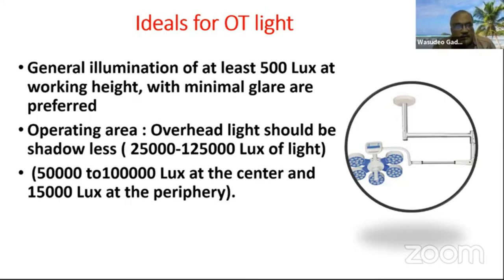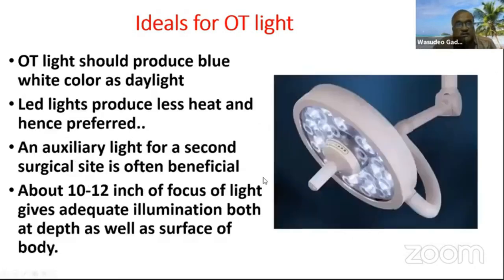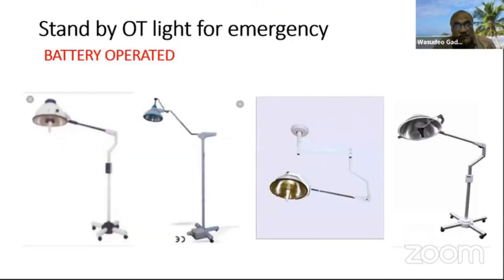The pendant system or breeder is ideal. The OT light should provide general illumination of at least 500 lux at working height with minimal glare. The operating area overhead light should be shadowless. OT lights should produce blue-white color like daylight. LED lights produce less heat. An auxiliary light for a second surgical site is often beneficial, and about 10 to 12 inches of focused light gives adequate illumination both at depth and at the surface.